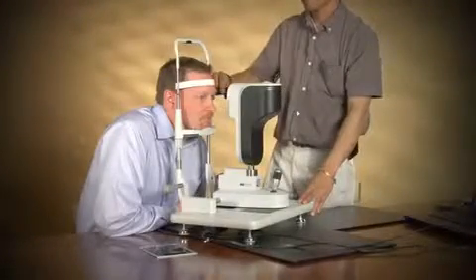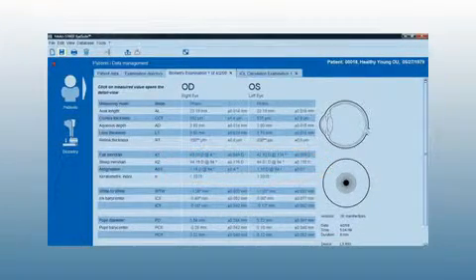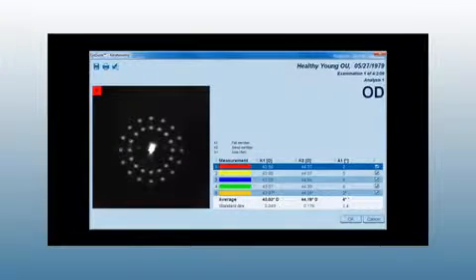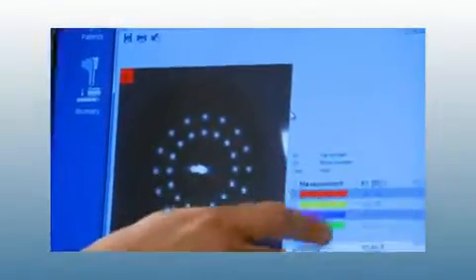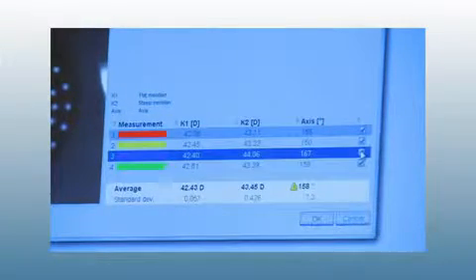LENSTAR is unique in regards to its keratometry. Compared to the other optical biometer, LENSTAR not only gives mean values for the magnitude of sphere, astigmatism, and its axis, but also includes standard deviations for each of those parameters for every recorded measurement. Studies have shown that when the standard deviation of the axis of each of the measurements is within a certain limit, LENSTAR keratometry is the best selection predictor for the type and power of toric IOLs targeted to correct astigmatism.